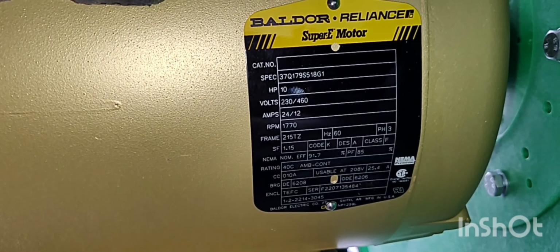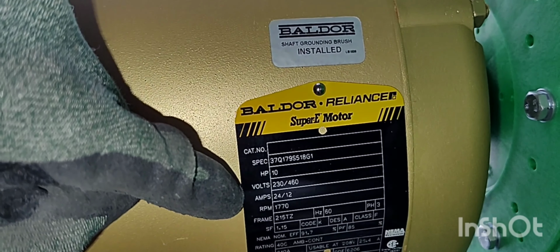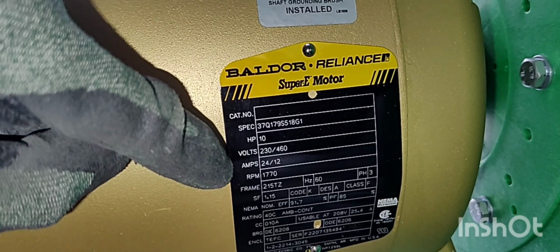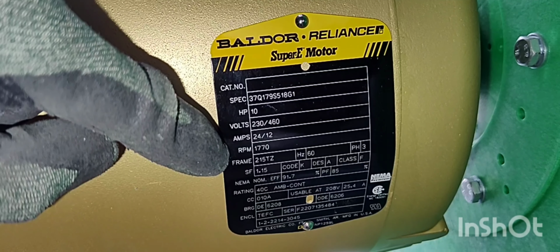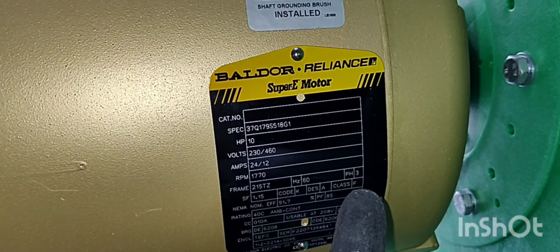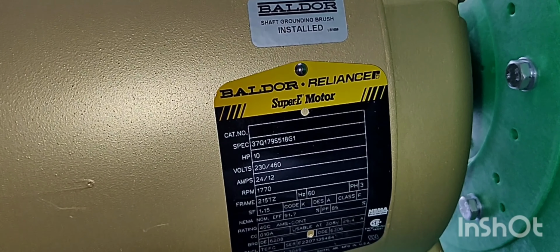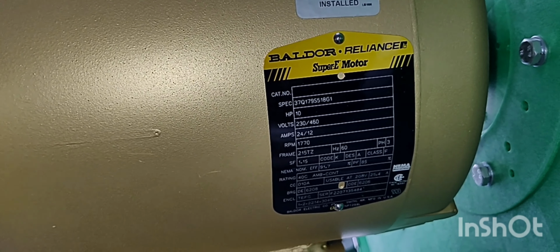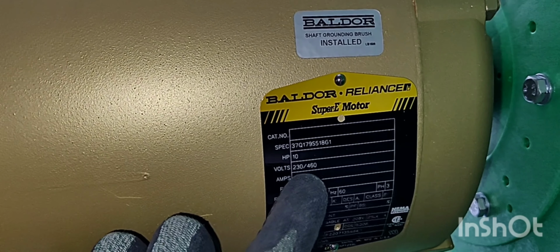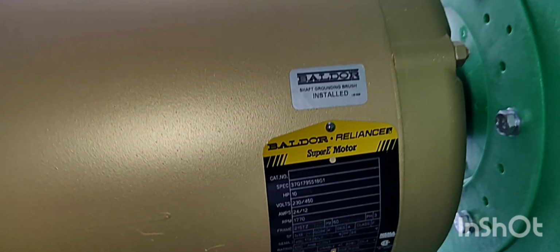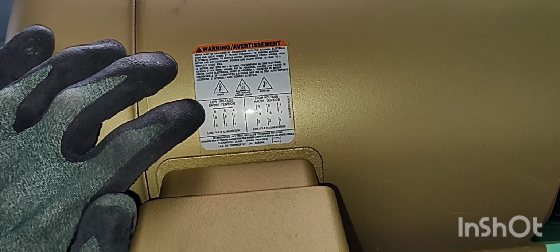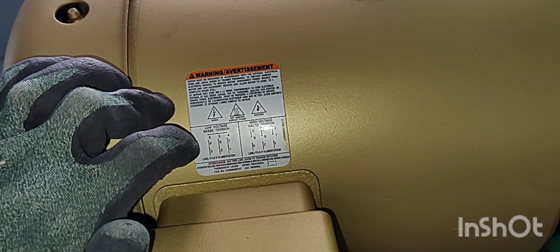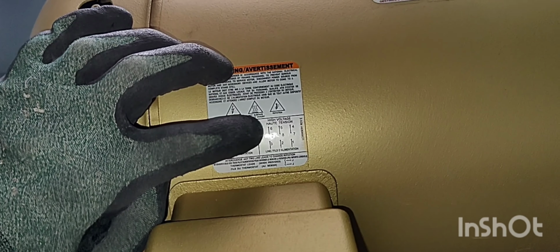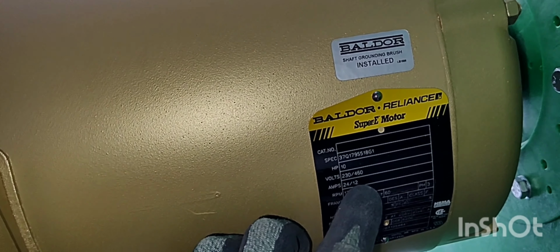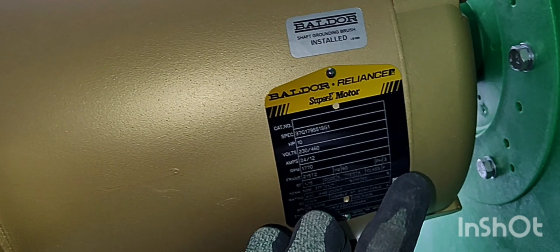Here is the nameplate. So if we are sizing our conductors, we're going to go off this 10 horsepower, voltage 230 or 460, amps 24 or 12, and we got 3-phase. And this other stuff, code K, class F, that is important, but not when we're sizing the conductors. Now if you'll notice, there's 2 voltages, 230 or 460, and 2 amperages, 24 or 12. Well, right here it shows that this is able to be tapped 2 different ways, high voltage or low voltage. That nameplate on that door, which I'll show you in just a sec, says it's tapped at high voltage. So we're going to come and read the high voltage, 460, and that's 12 amps, 10 horsepower, 3-phase.